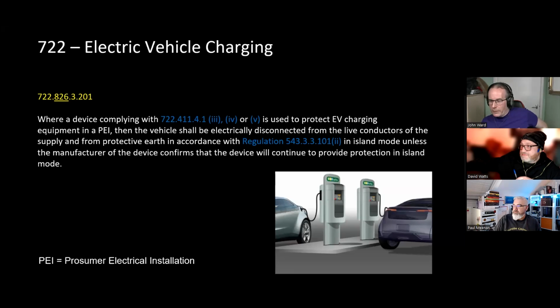Essentially, where a device complying with those standards is used to protect EV charging equipment, and a PEI, which is a prosumer's electrical installation, then the vehicle shall be electrically disconnected from the live conductor supply and from protective earth in accordance with that regulation. And this is in island mode. This is where you're going to be running your house from your battery storage and you're disconnected from the grid. We'll look at that in a moment. The disconnection of protective earth is pretty much going to happen with many of these supply points anyhow, so it doesn't actually change a whole lot. It's basically been put in there just to fit in with part 8, which we'll look at in a moment.